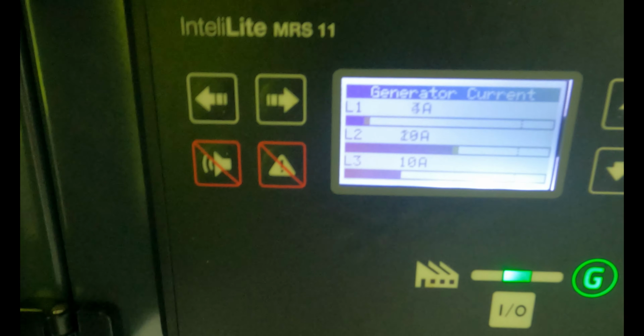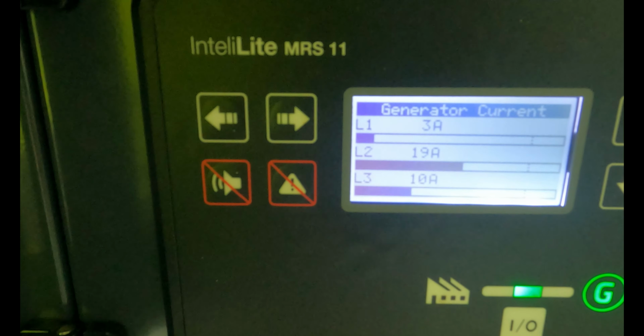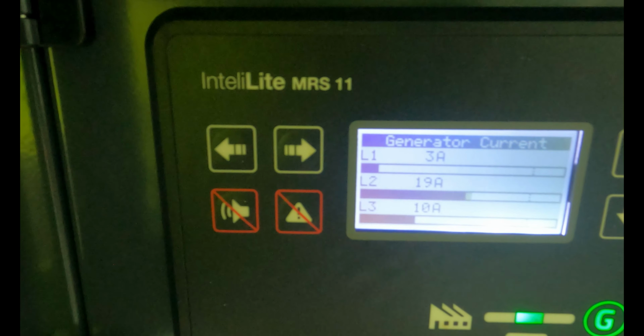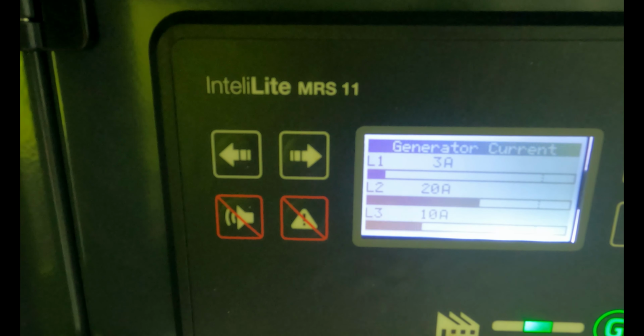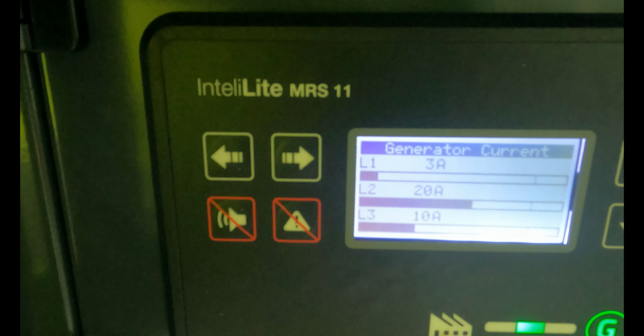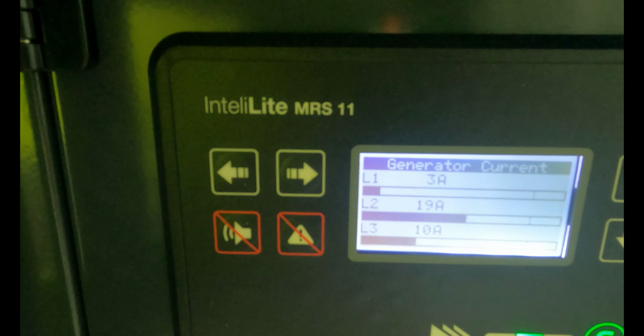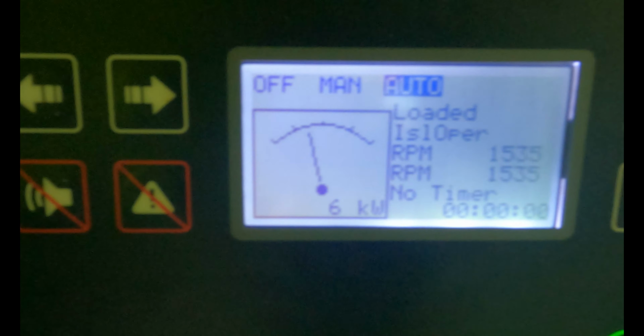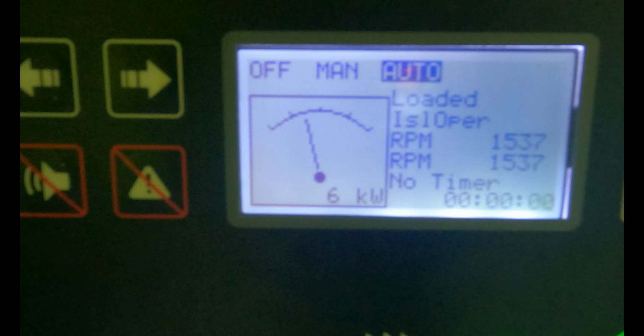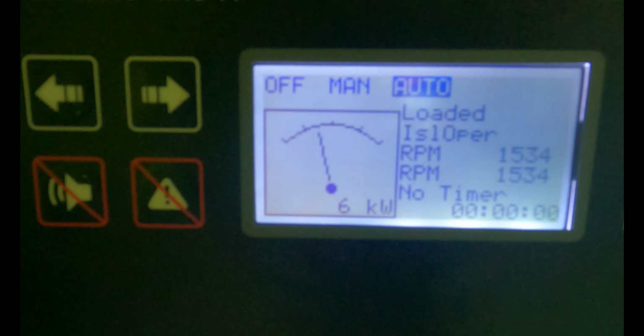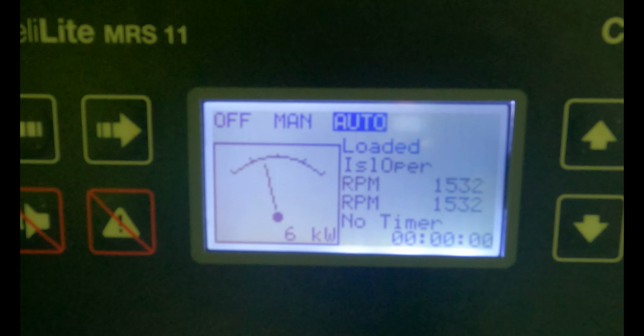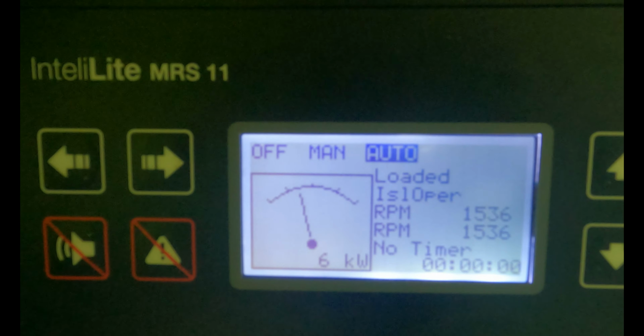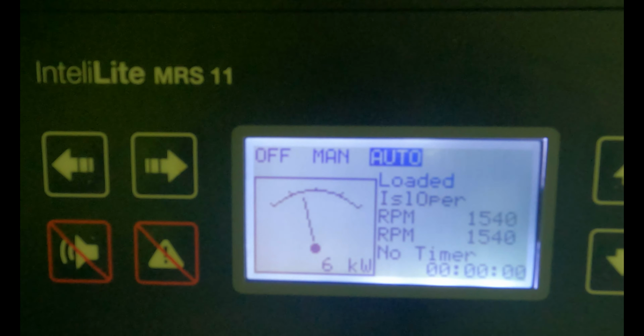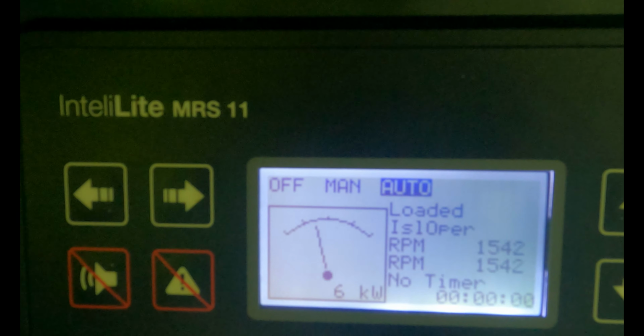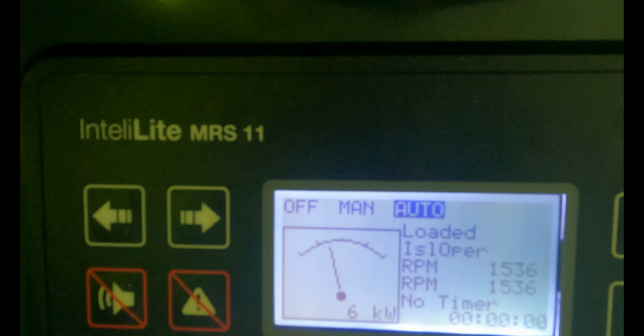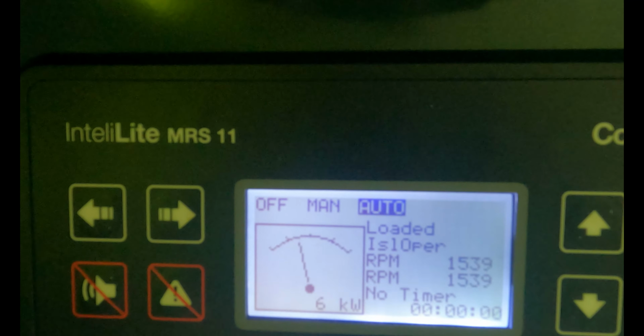Okay, so I just got back from the house and I put a dryer on up there, and I made sure both ovens are cranked up. So here we are, 19-20 amps on L2, 10 amps on L3. What this is telling me is that 6 kilowatts is being used on the generator. Keeping in mind, it will supply 19. So it's well and truly within an easy load.